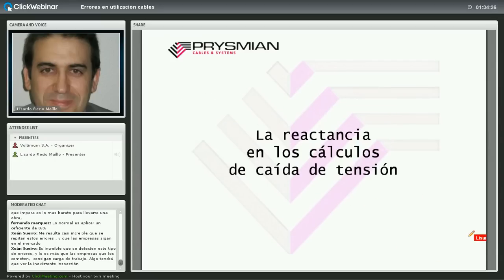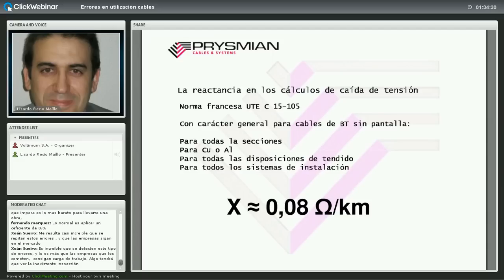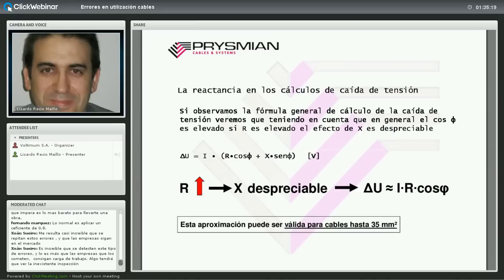La reactancia en los cálculos de caída de tensión: la norma francesa UTE C15-105 establece que para cables de baja tensión sin pantalla, para todas las secciones, cobre y aluminio, y para todos los sistemas de instalación, el valor general de reactancia es 0,08 Ω/km. Independientemente de si los cables están en monofásica, trifásica, en tresbolillo o en un plano, podemos aplicar este valor. Los cálculos analíticos confirman que casi siempre el valor ronda 0,08 Ω/km. Se recomienda considerar la reactancia a partir de secciones de 35 mm².